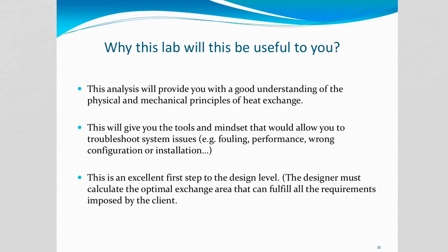If you don't design systems, there are many times where you will have, as an engineer, to troubleshoot some issues. It could be during startup, the heat exchanger is not connected properly, they inverted the inlet and the outlet, or it gets dirty and performance goes down. All sorts of reasons why. What you will see today will make you think properly regarding the reason why our system doesn't work.